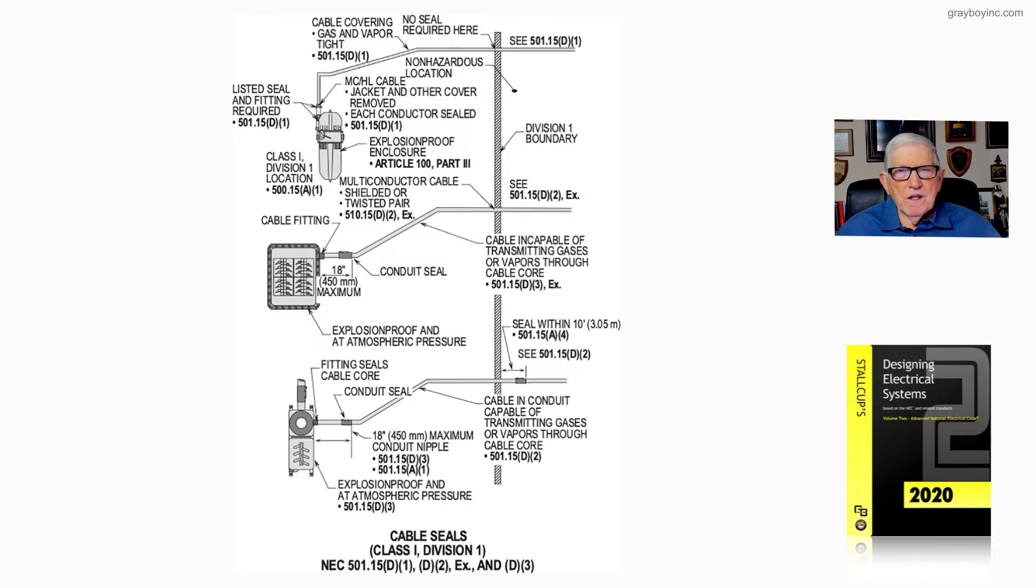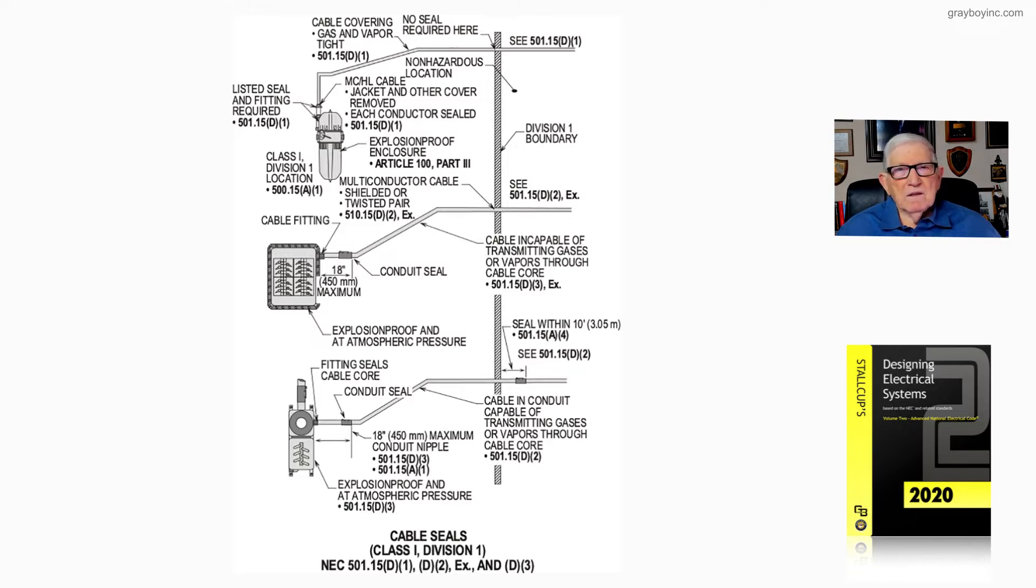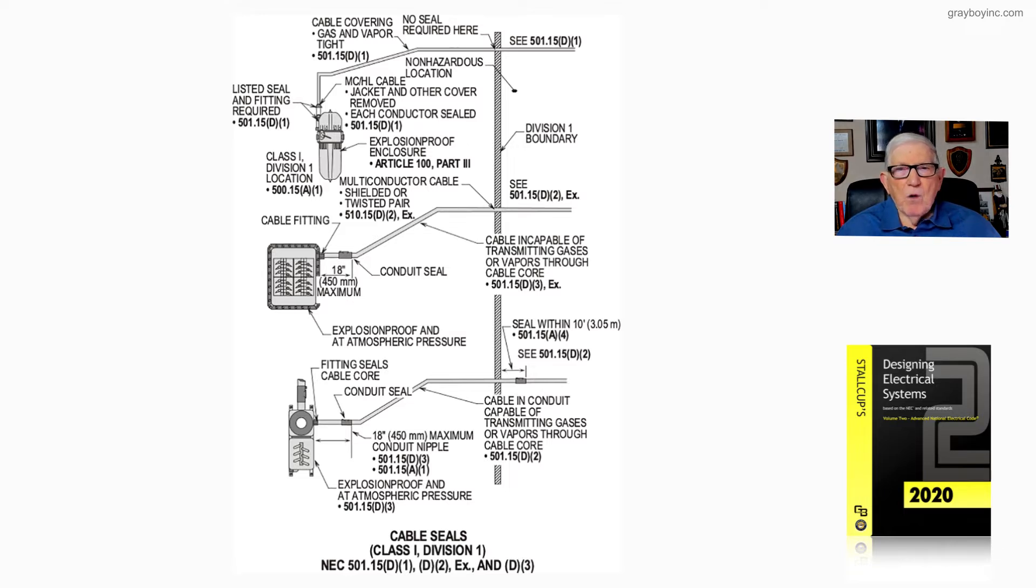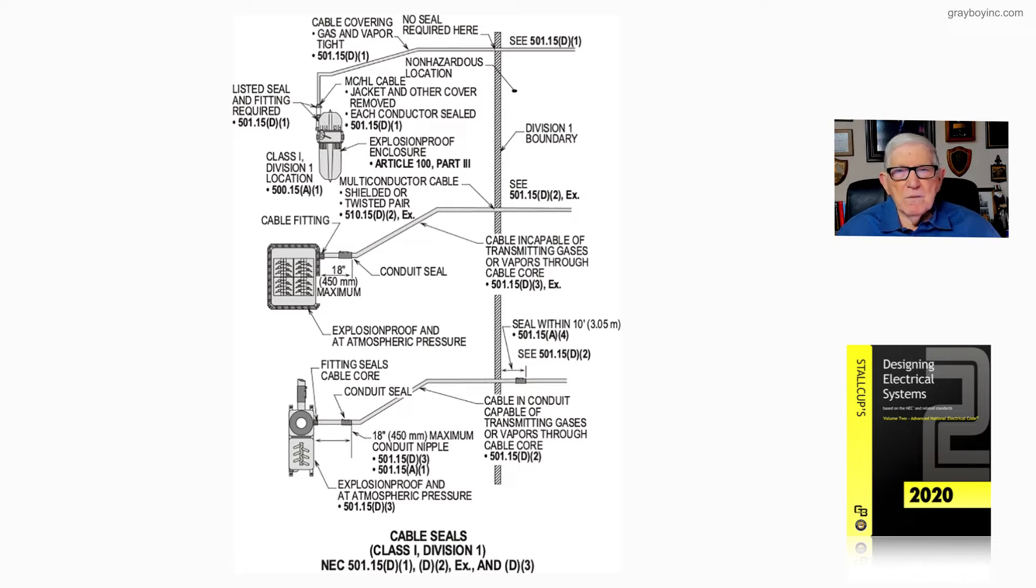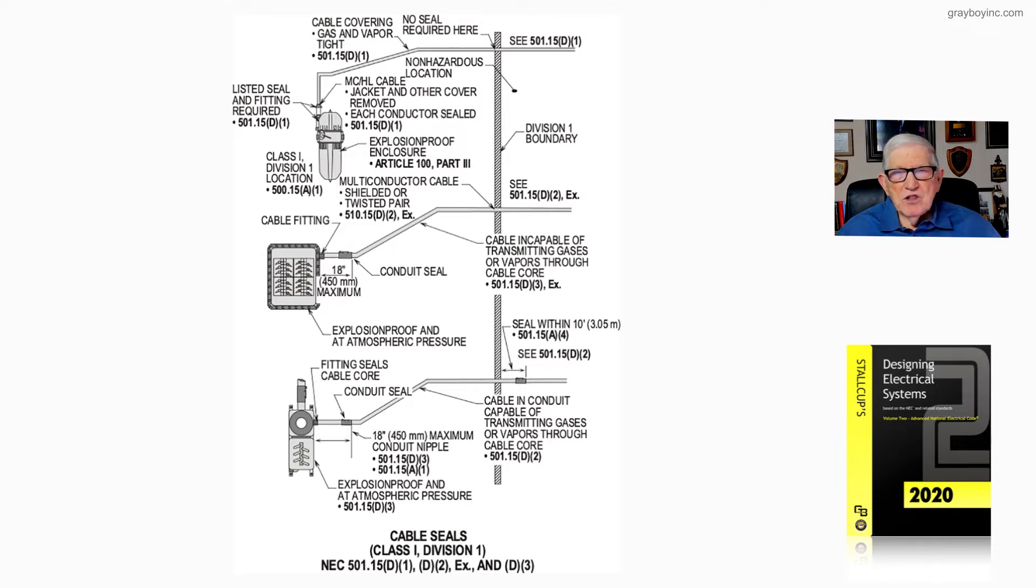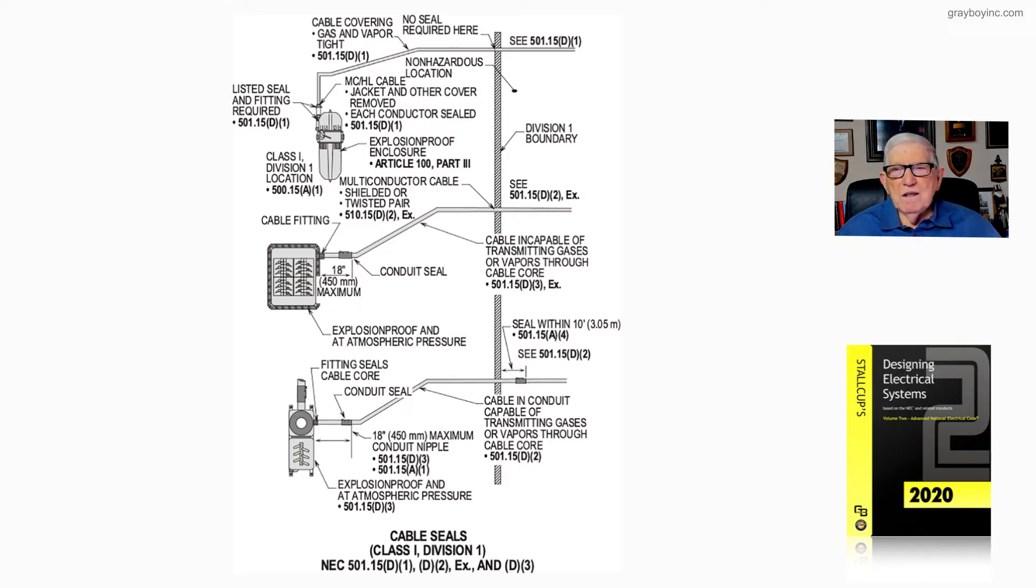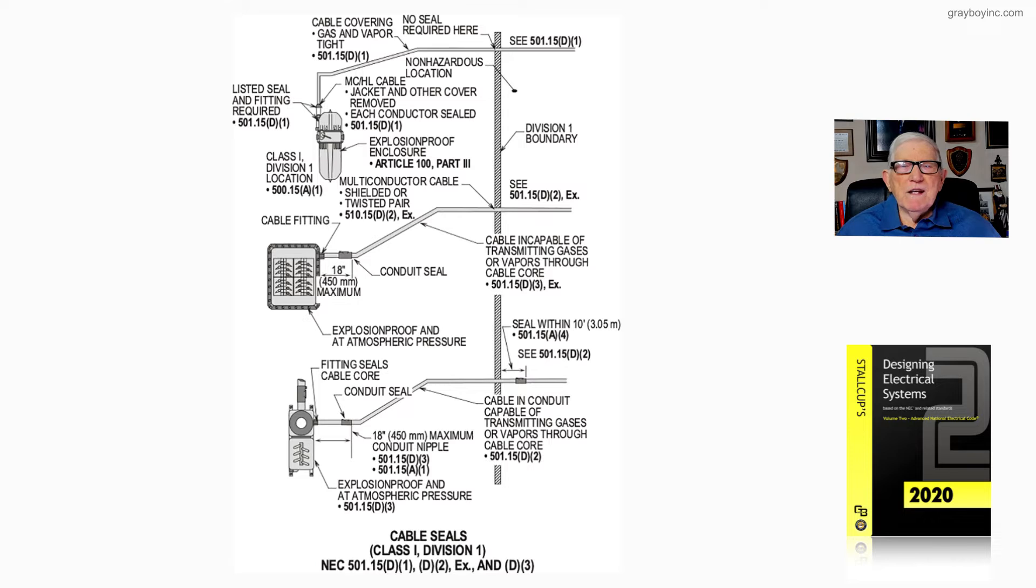In Article 100 Part 3, we have the enclosure explosion-proof defined and wiring methods defined in the 300 series. Notice the next cable below it is a multiple conductor cable, shielded or twisted pair. Once again, notice that we do not have to cut that shield and create an unwanted noise problem.